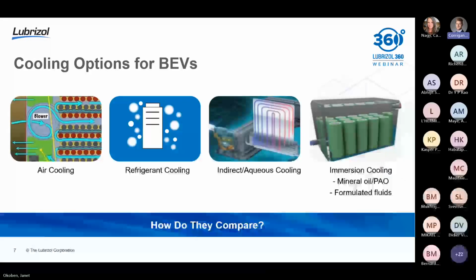Getting a little bit more sophisticated, we have our indirect cooling methods. So this can be refrigerant cooling or an indirect water glycol type cooling system. So in both of these systems, we have a cooling fluid that's piped through a cold plate that can reduce the temperature of the cold plate and then conductively withdraw the thermal energy from your battery pack. So refrigerant cooling typically uses a refrigerant in a two-phase system, so it uses evaporative cooling to cool the cold plate. It has some limitations in that it typically uses fluorinated types of chemistries, which are known to have poor global warming impacts, as well as it's limited by the ability to only cool but not heat, because you can't use a refrigerant to warm the battery if you're in a cold environment.